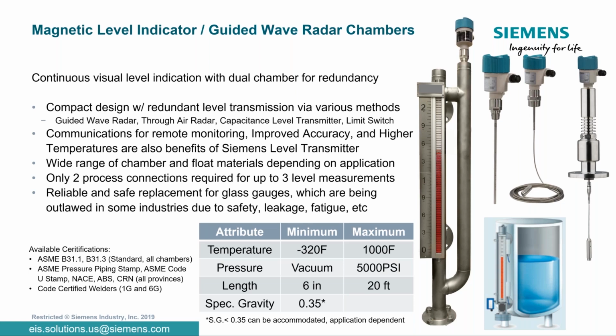So in this particular case, you can have it with a guided wave radar, the local indication, or even a rod chain transmitter or a level limit switch. But this is a direct replacement for gauges or glass gauges that you already have out in the field, as a retrofit, giving you local indication as well as the ability to communicate that back.